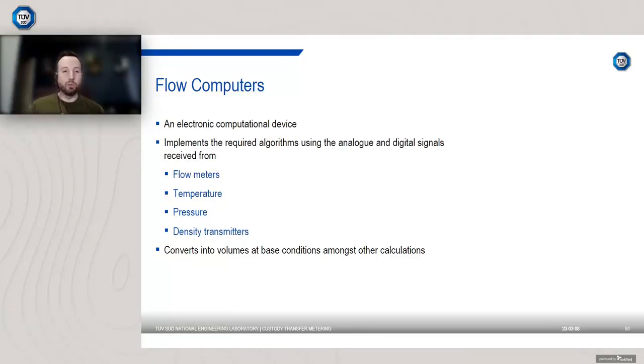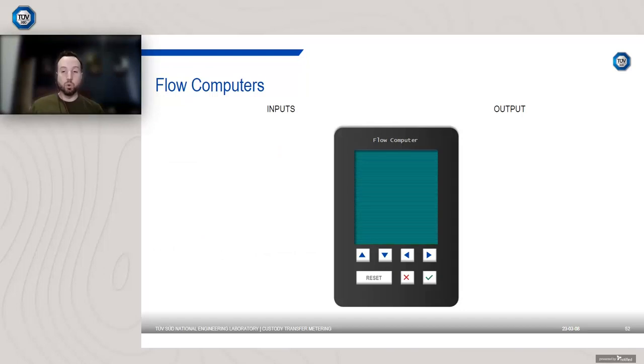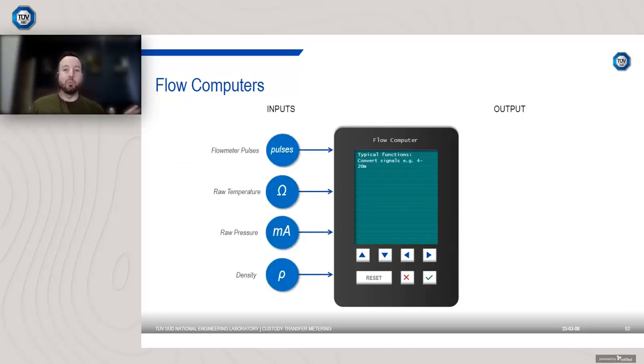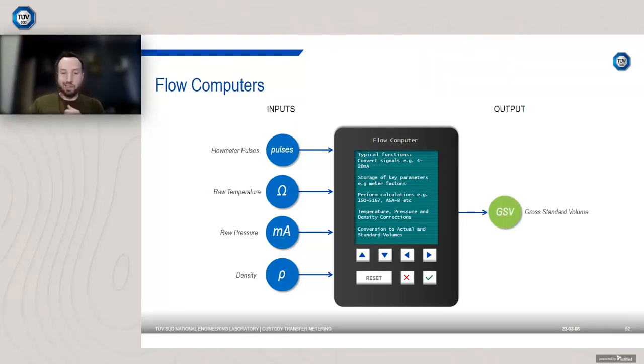I'm just going to quickly finish on flow computers. So these are a really critical part of custody transfer metering. And what they do is they implement the required algorithms using all the various analog and digital signals received from your flow meters, your temperature, your pressure instrumentation, your density devices, and it will do things like convert into base conditions amongst other calculations. So as a typical example, the flow computer might take in the pulse train from your flow meters, take in 4-wire resistance, might record raw pressure from a transmitter in milliamp, might take in density, takes all these signals, converts them.